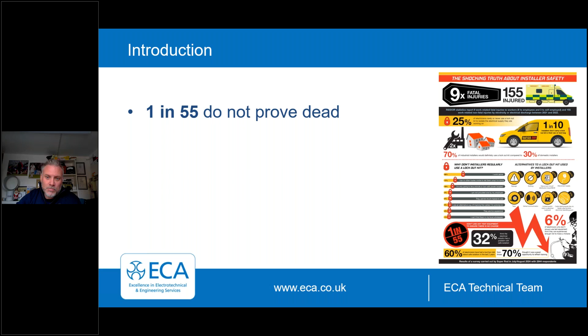To highlight from these stats, this is a summary from SuperRod as part of their Safe Isolation campaign held earlier this year in July and August 2024, with just under 3,000 responses. Out of those 3,000 responses, 1 in 55 do not prove dead, 1 in 10 didn't carry a lock-off kit, and 25% rarely or never lock out. There was also a split between domestic and commercial: 70% of those who responded lock out circuits commercially, compared to 30% in domestic settings.